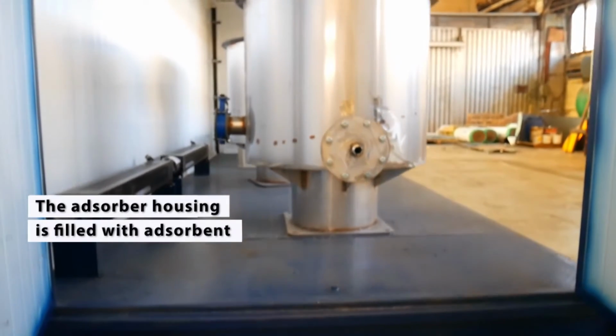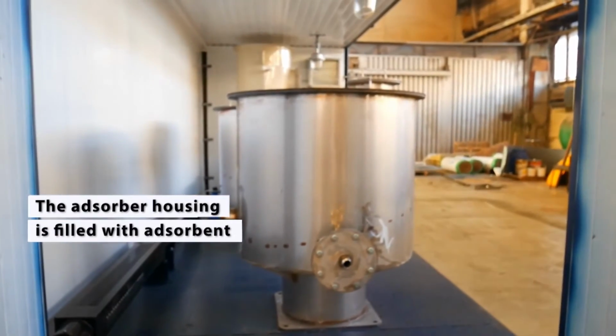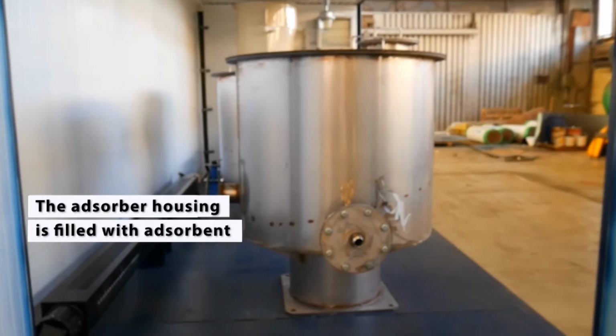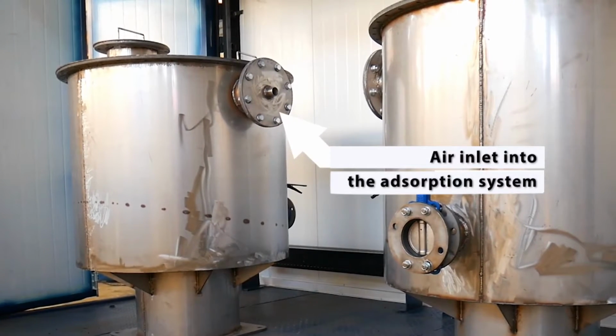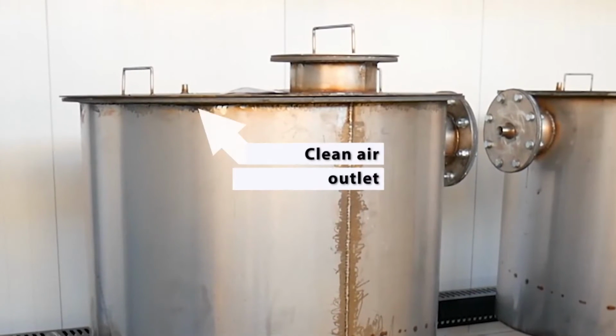The adsorber housing is filled inside with adsorbent. The adsorbent is a special activated charcoal, synthetically activated charcoal. Contaminated air enters the adsorber and is distributed through the special small channels as evenly as possible over the entire area, and the whole surface of the adsorbent. The adsorbent absorbs all the molecular contaminants. Meanwhile, clean air passes to the outside and leaves the adsorbent. Afterwards, it passes further to outdoor areas, or wherever you cast it. Then, back to the room.